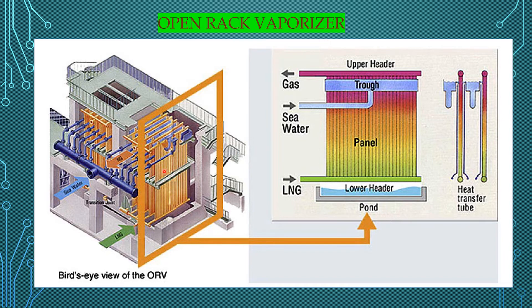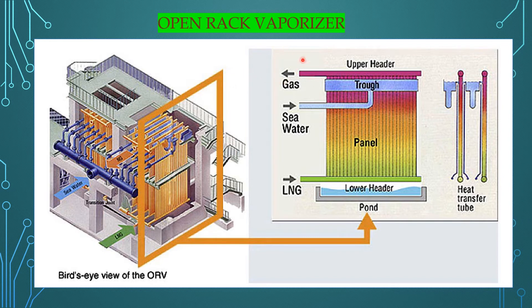Now we can see the schematic diagram of the open rack vaporizer — the top view and side view, whether in an FSRU or offshore plant. LNG is admitted at the bottom of the ORV through aluminum alloy tubes, flowing from bottom to top. Seawater is admitted from the top over the tubes, flowing top to bottom, and then sent back to sea. The flow is counter-current, and the converted natural gas is collected and sent to onshore facilities for further treatment.